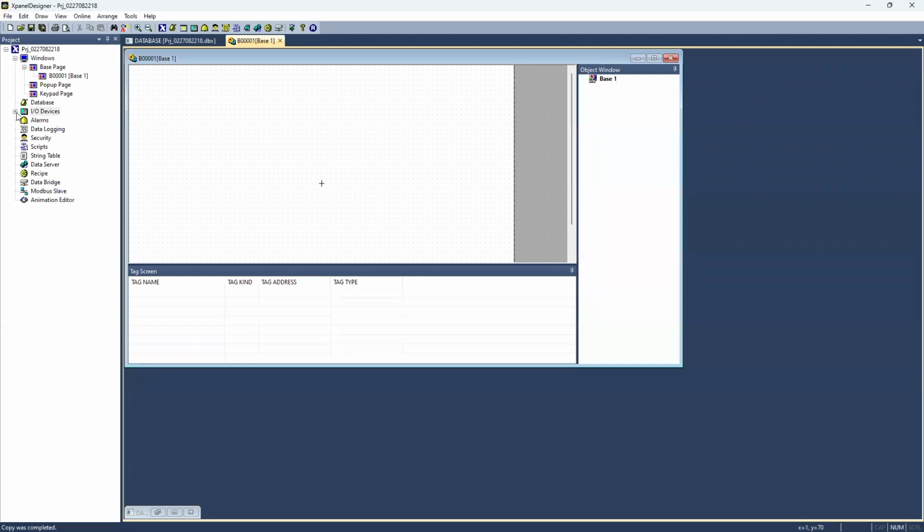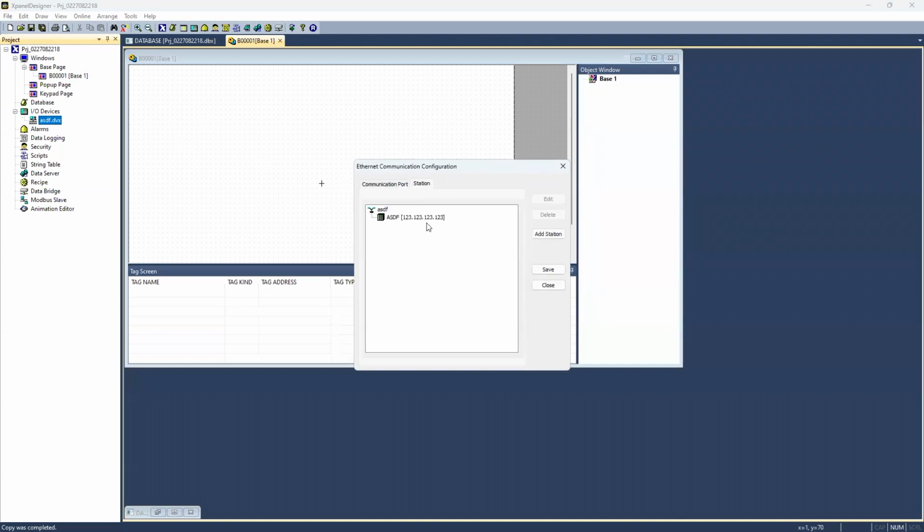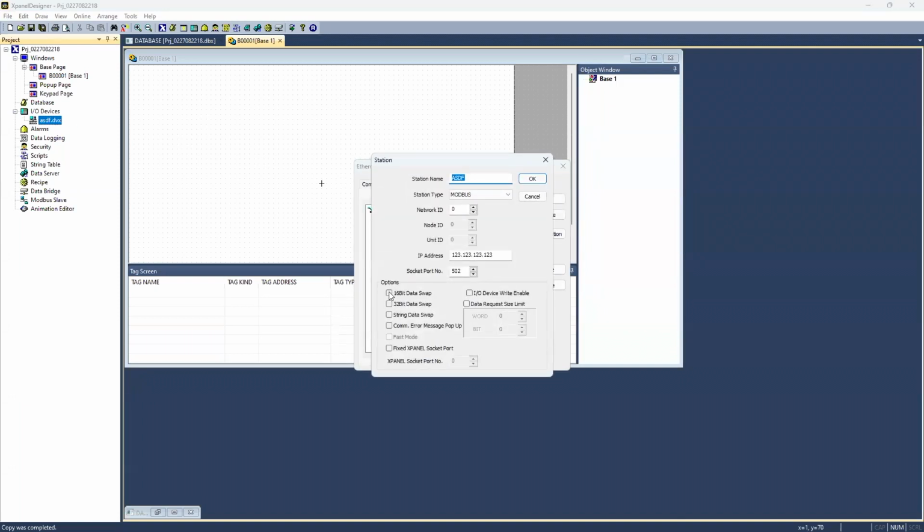Now, if you do not get the correct value, regardless of choosing float, that might be a little endian, big endian issue. And with that, we support 16-bit and 32-bit data swap. So that might be the case. It might be a little endian, big endian type complication. And like I mentioned earlier, ModBus is open source, so different companies do things differently. You can just take that into consideration if you're getting the wrong value. It might take a little bit of troubleshooting, but once you get there, you'll be fine.